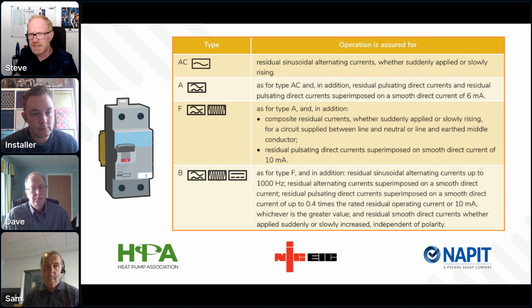And again, I know we keep stressing this, but I would say if a manufacturer's instructions come, and we need to speak to the manufacturers more and more, if a manufacturer is specifying a type of RCD and you as a designer have looked at that installation and said, well, actually the supply to that I can get on an external wall, there's no way that cable's ever going to get damaged or penetrated by a screw, call the manufacturer and ask for the rationale why they're asking for an RCD. You might not get through to a technical team, I'm going to be honest, but actually with the decent manufacturers, the big players in the game, they will have technical people that will explain the reason why they are recommending an RCD is installed.